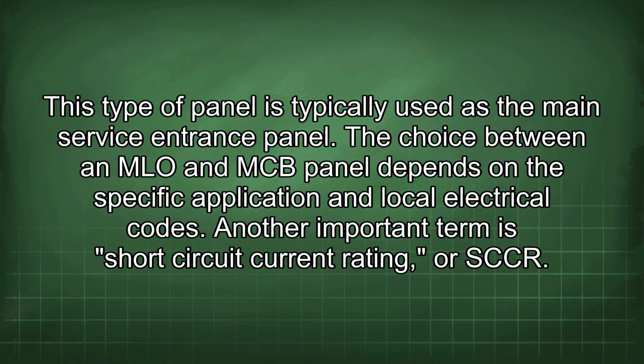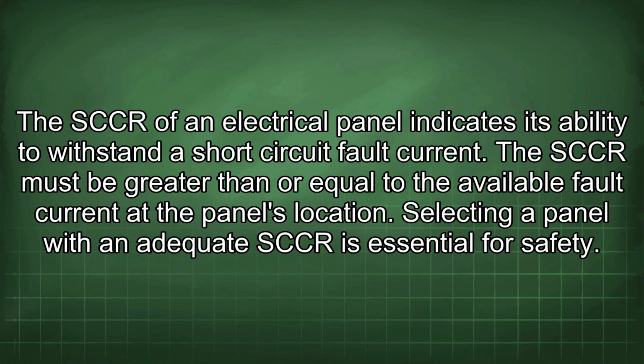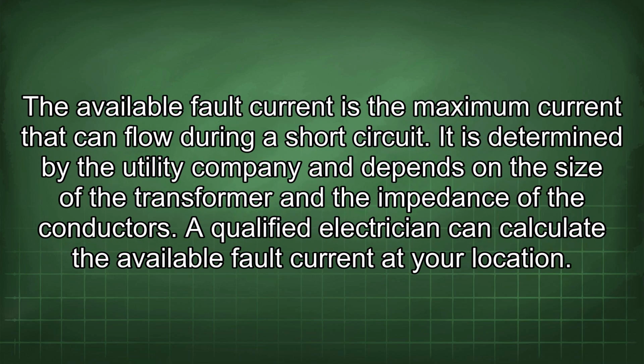Another important term is short circuit current rating, or SCCR. The SCCR of an electrical panel indicates its ability to withstand a short circuit fault current. The SCCR must be greater than or equal to the available fault current at the panel's location. Selecting a panel with an adequate SCCR is essential for safety. The available fault current is the maximum current that can flow during a short circuit. It is determined by the utility company and depends on the size of the transformer and the impedance of the conductors. A qualified electrician can calculate the available fault current at your location.